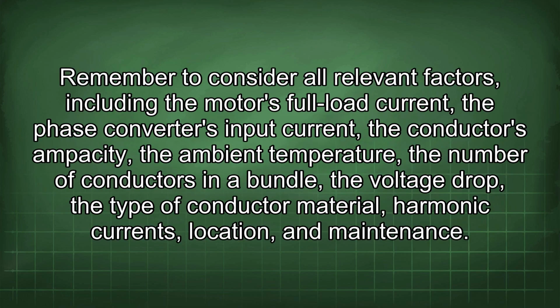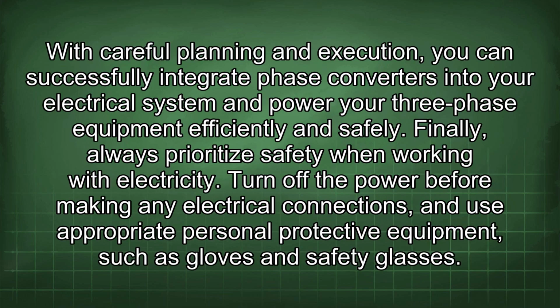Remember to consider all relevant factors, including the motor's full load current, the phase converter's input current, the conductor's ampacity, the ambient temperature, the number of conductors in a bundle, the voltage drop, the type of conductor material, harmonic currents, location, and maintenance. With careful planning and execution, you can successfully integrate phase converters into your electrical system and power your three-phase equipment efficiently and safely.